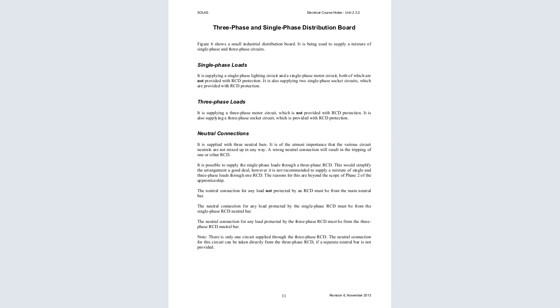3-phase and single-phase distribution board. You can see figure 6 shows a small industrial distribution board. It is being used to supply a mixture of single-phase and 3-phase circuits. The single-phase loads: it is supplying a single-phase lighting circuit and a single-phase motor circuit, both of which are not provided with RCD protection. It is also supplying 2 single-phase socket circuits which are provided with RCD protection.